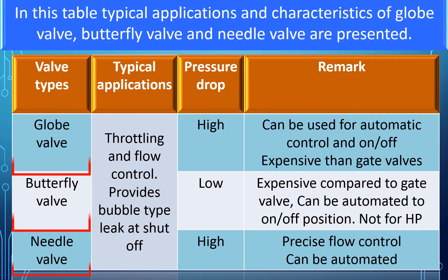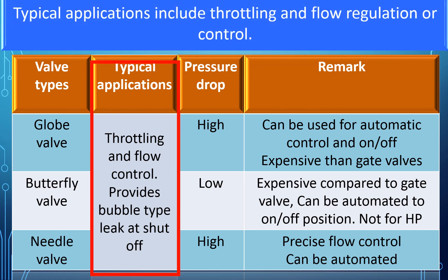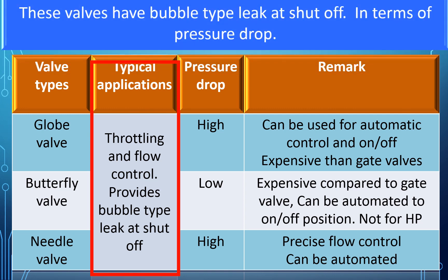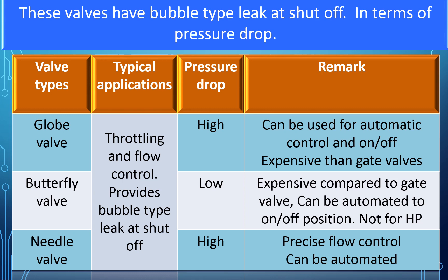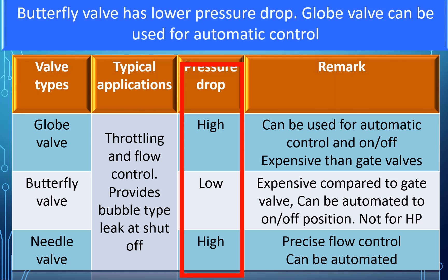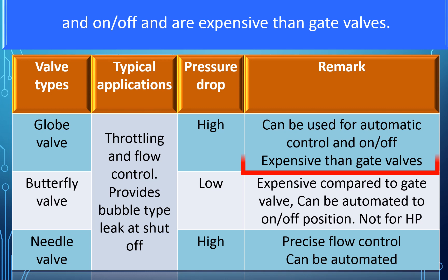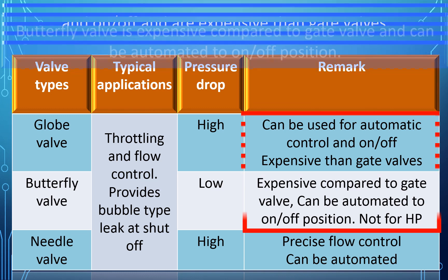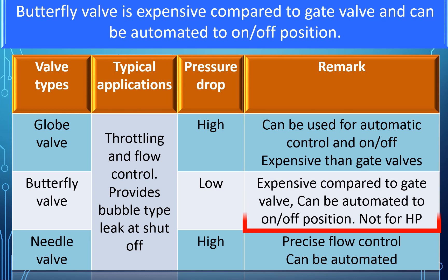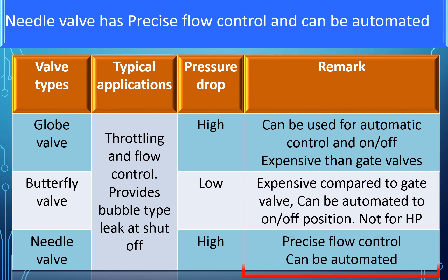This table presents typical applications and characteristics of globe valves, butterfly valves, and needle valves. They can be used for all types of chemicals, both liquid and gases. Typical applications include throttling and flow regulation or control. Globe and needle valves have higher pressure drop due to their design, while butterfly valves have lower pressure drop. Globe valves can be used for automatic and on-off control, and are more expensive than gate valves. Butterfly valves can be automated to on-off position, and needle valves offer precise flow control and can also be automated.